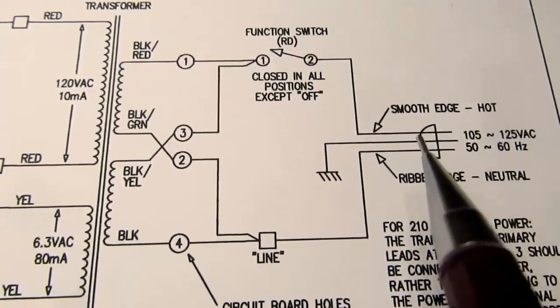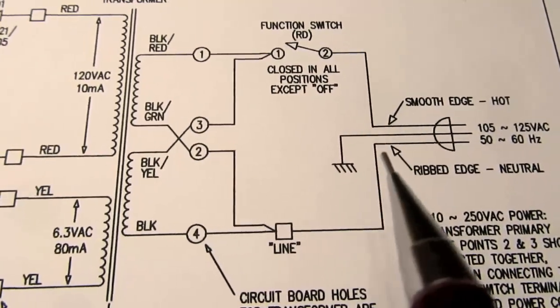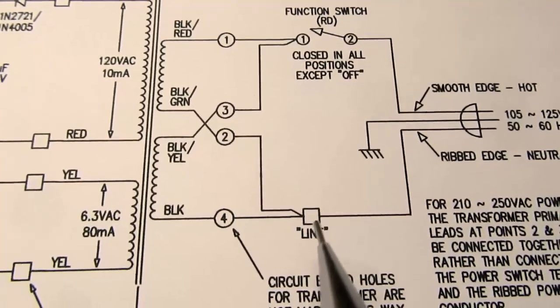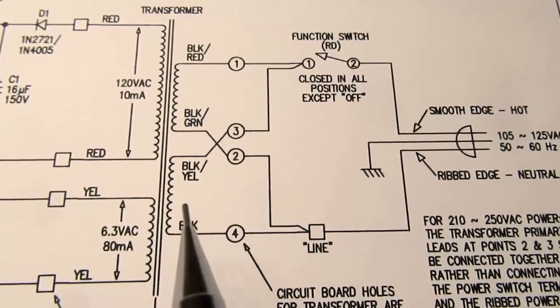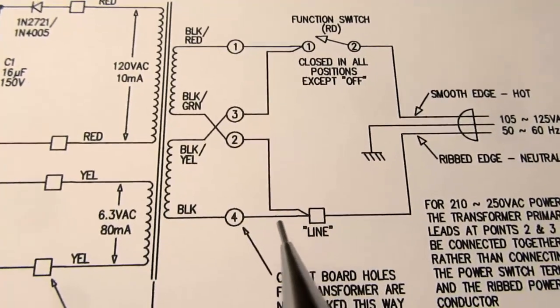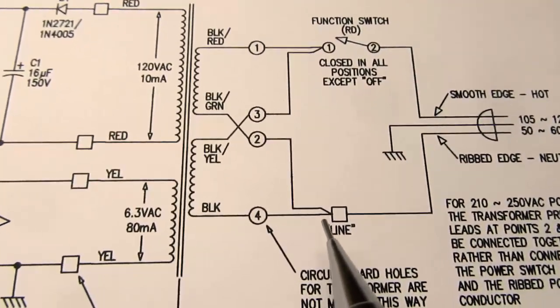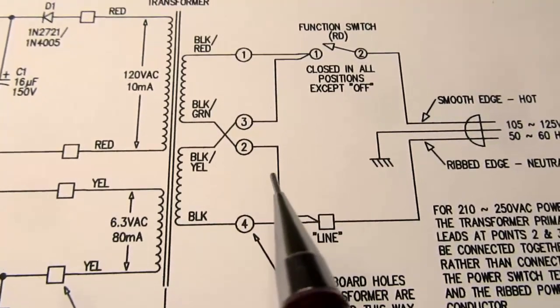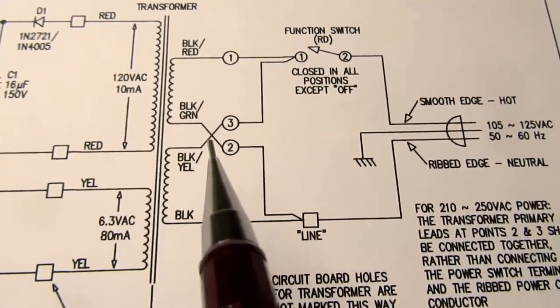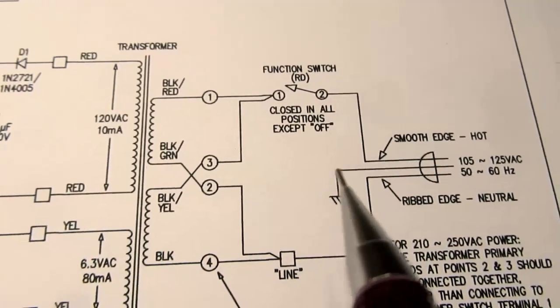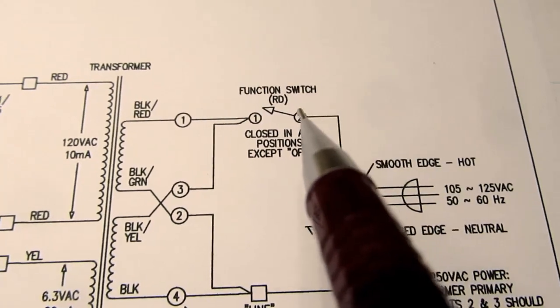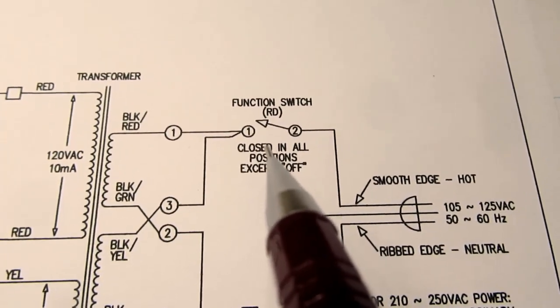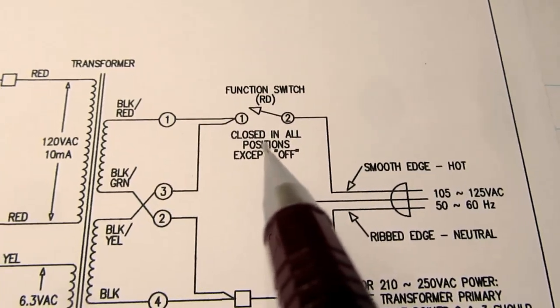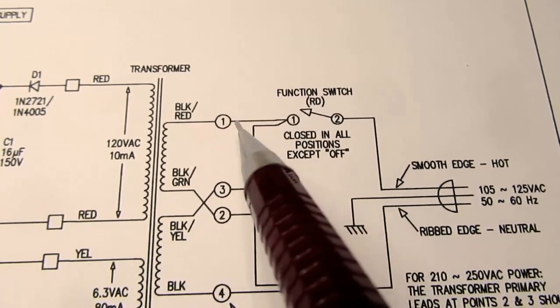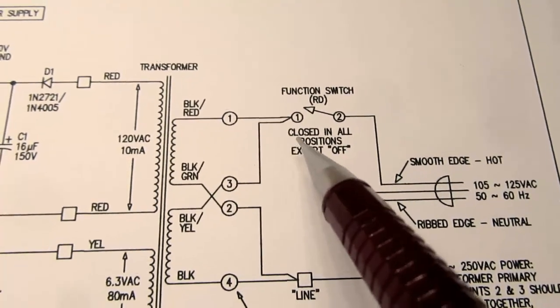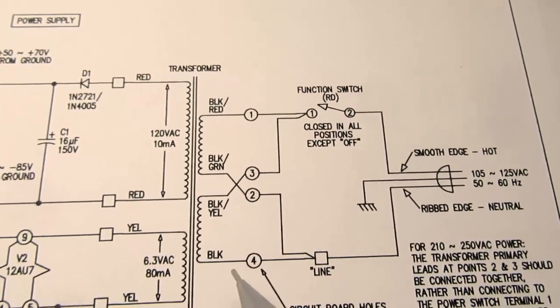We have the incoming AC line cord. The neutral is connected to the circuit board at a hole called line, and from there either 1 or 2 transformer primary connections are made by just soldering the wires into a hole that's adjacent to the hole where the line cord goes into. In the case of the 120 volts, it's these 2 wires, the black, green, and the black, go to there. And then the hot side of the line cord goes up through the power switch, which is just one of the contacts on the rear deck of the function switch, which is closed in all positions except for the off position. And then that has the remaining transformer primary wires going directly to it. So when you close the switch, you energize the primary windings.